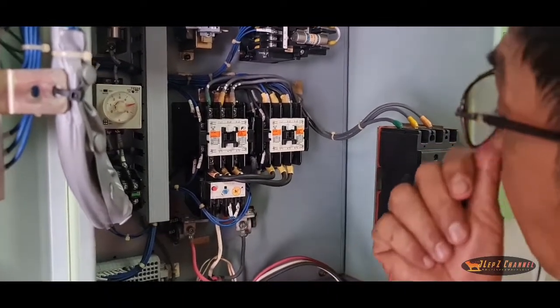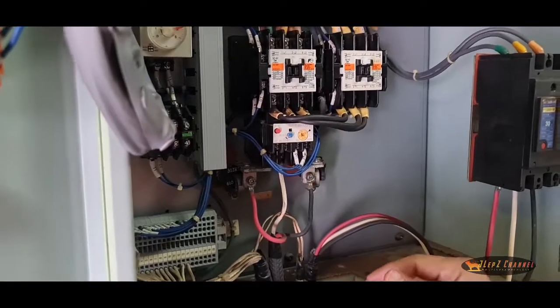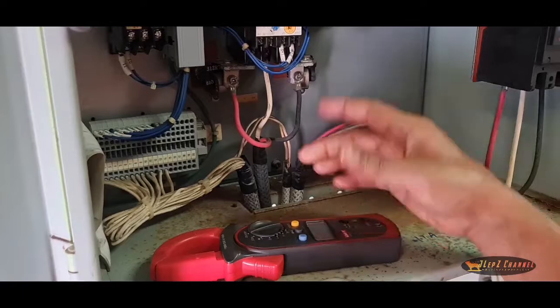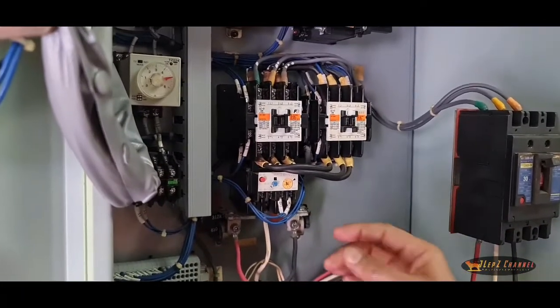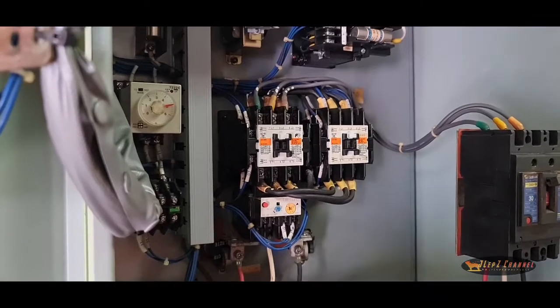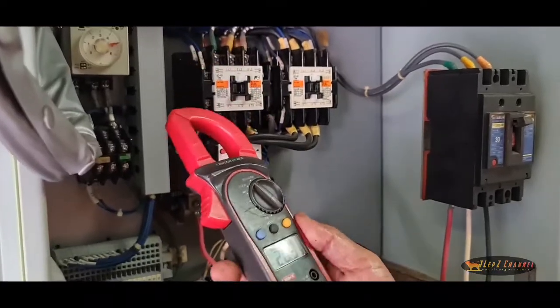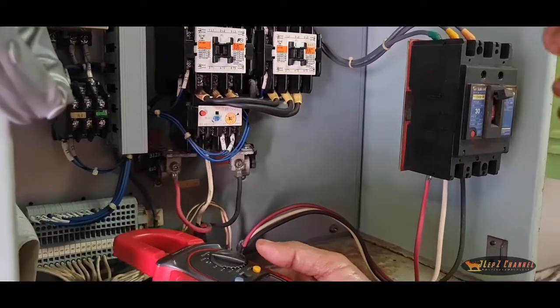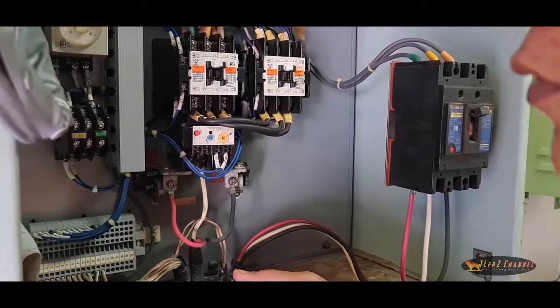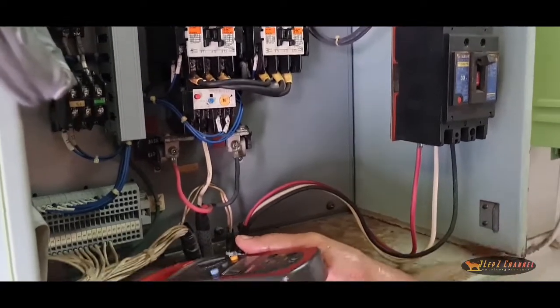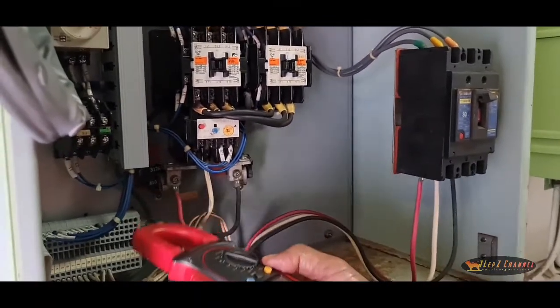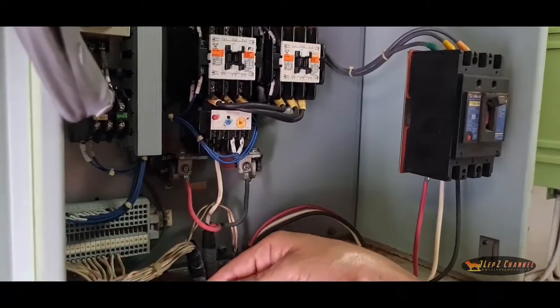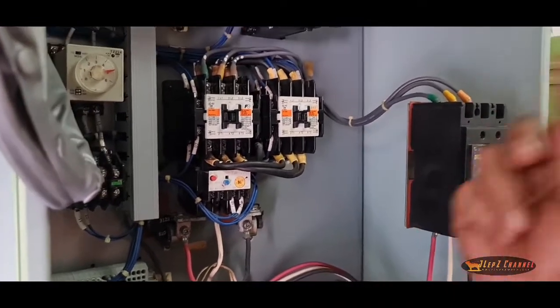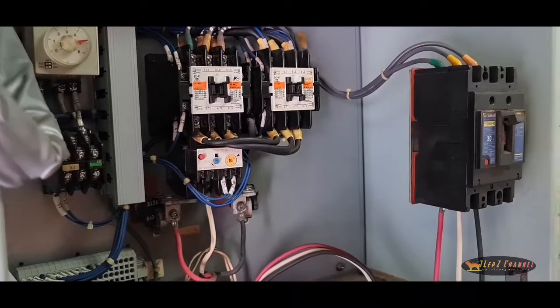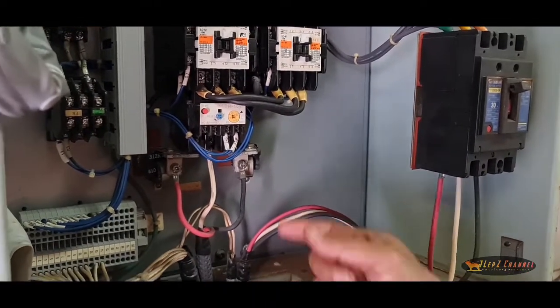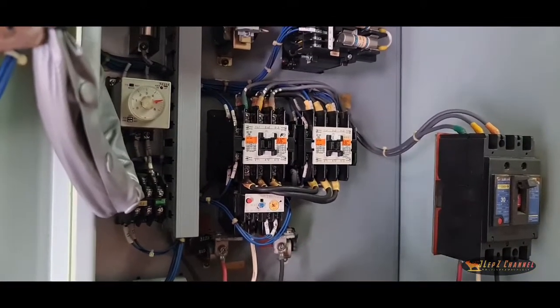So back to our knowledge of why we are using this clampmeter. Now we get how to set the overload relay by knowing the line current, which is a maximum of 21 amperes, times 140% as the allowable overload setting of the overload relay. That gives us a maximum of 29 amperes. Our setting here is 26, so it is still safe. Yesterday it tripped again, but nothing happened. It tripped off by itself, then it ran by itself.